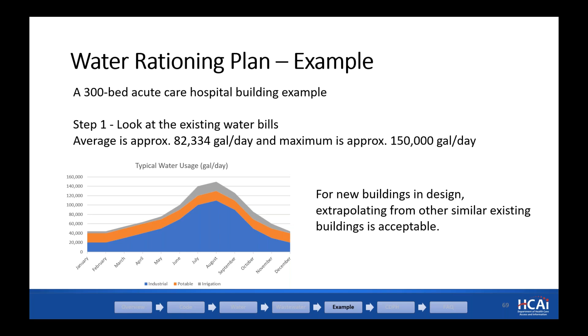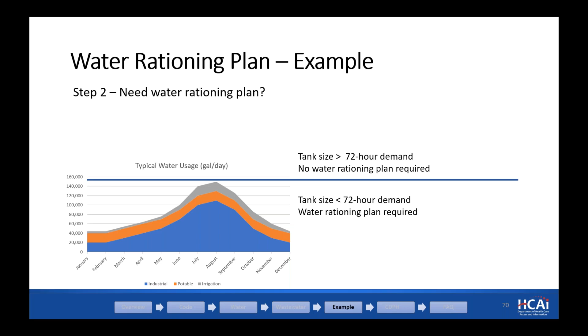The next question would be, do we need a water rationing plan? Well, if you can put in a tank size which is greater than the 72-hour demand, you do not need a water rationing plan. You are already continuing operations in a normal fashion. But a lot of facilities do not have that option because of site constraints or cost. If your tank size cannot be that much and it's less than the 72-hour demand, then a water rationing plan is required. So for this hypothetical case, a 300-bed hospital at 50 gallons per day per bed for 72 hours, the demand would come out to be 45,000 gallons. That's the minimum per code requirement.